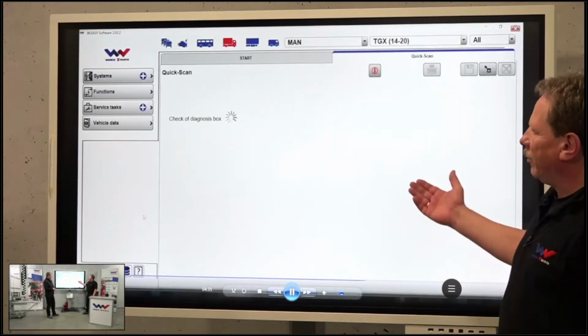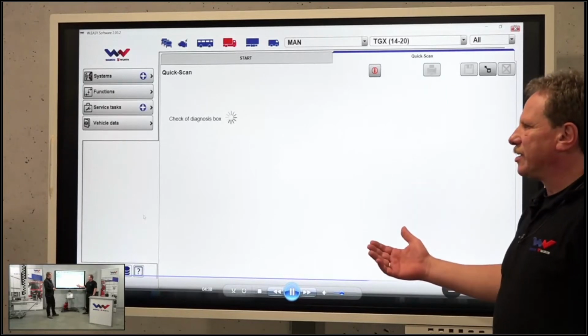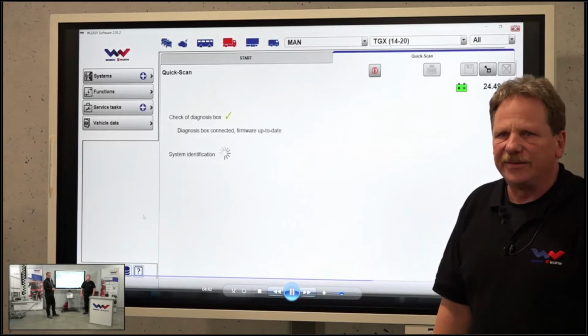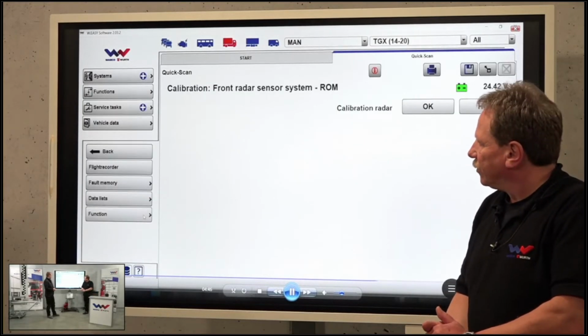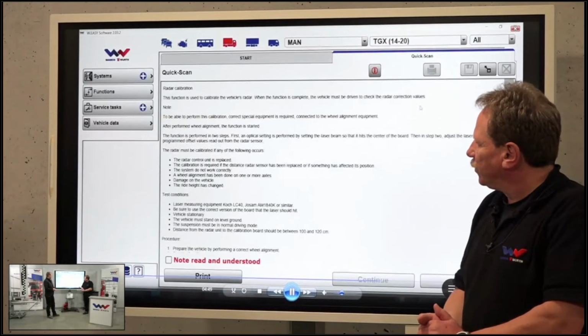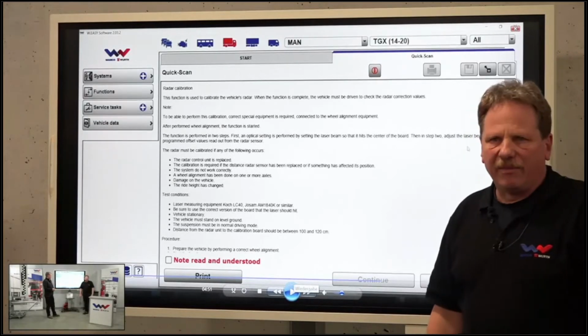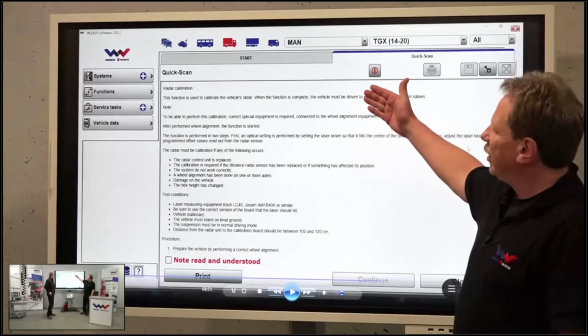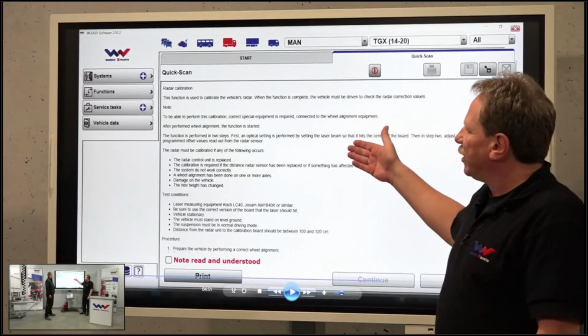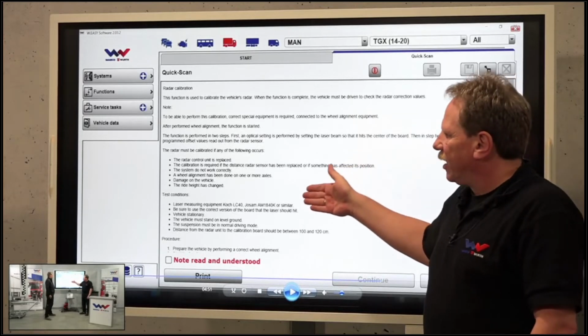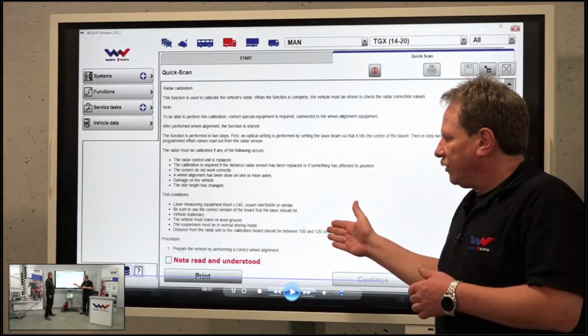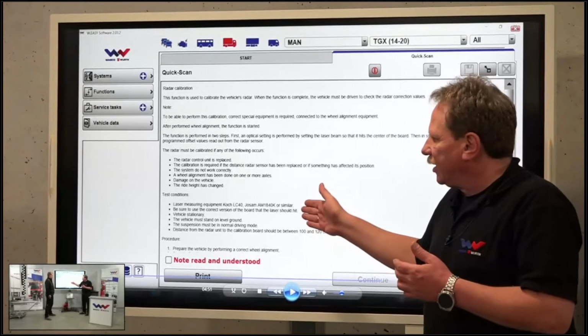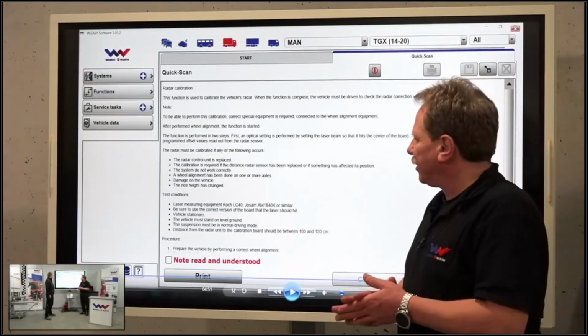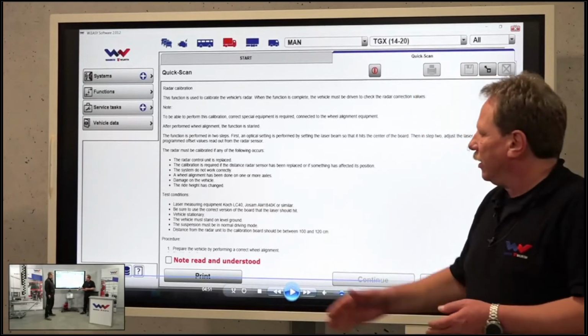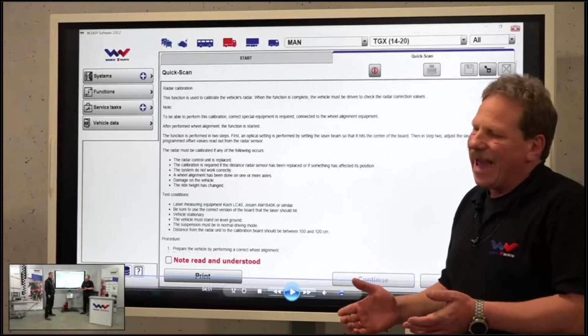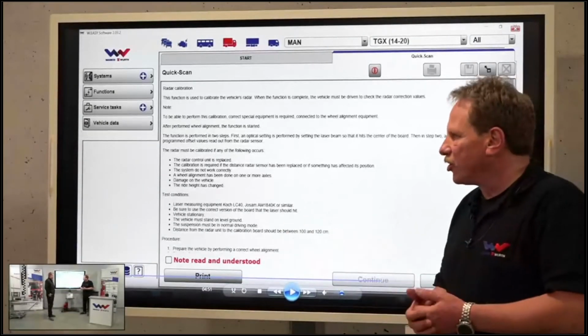We are going now towards the calibration, going out of the scan, going into the system directly, connecting the system together. Here we have the calibration, and as usual in our help files or calibration files, we have the explanation why it has to be done. We have the explanation when we have to do it, in what cases, the test conditions, but actually at the moment we still have in the help file the data of the OE tools. So it's the data from the Koch or from the Josam tool. How to set it up here? We will add a new help file which will include our new solution as well.